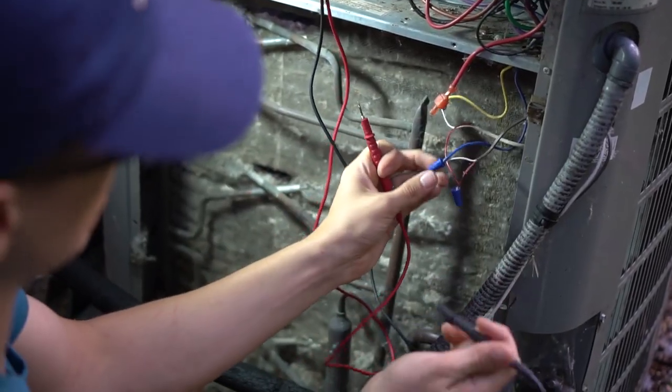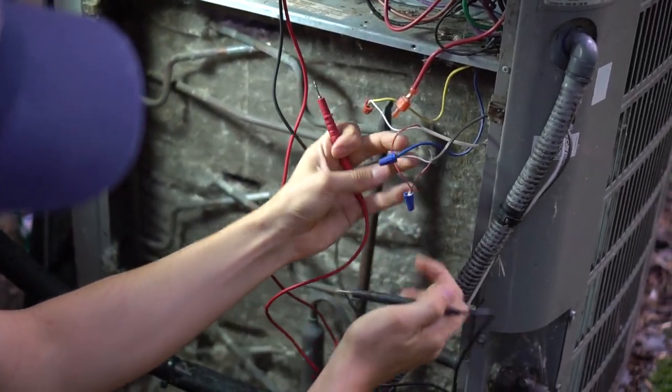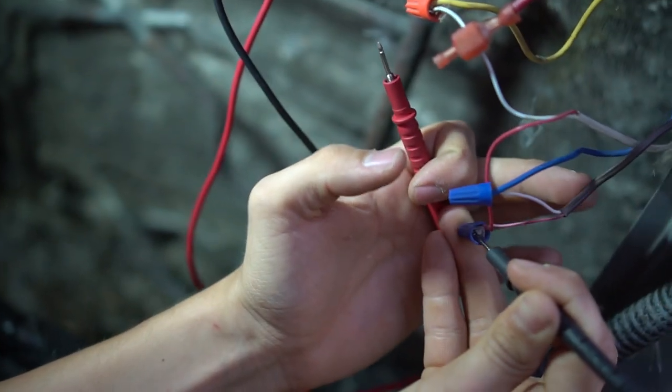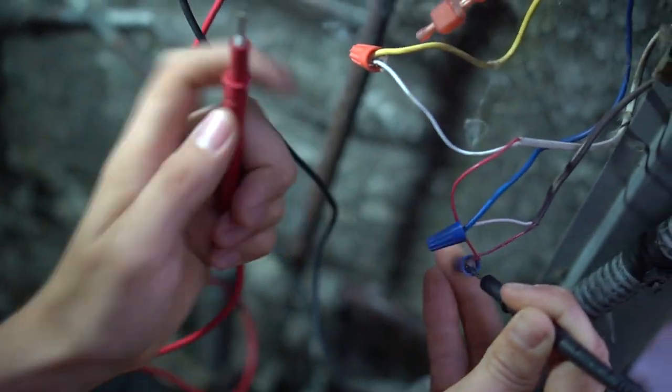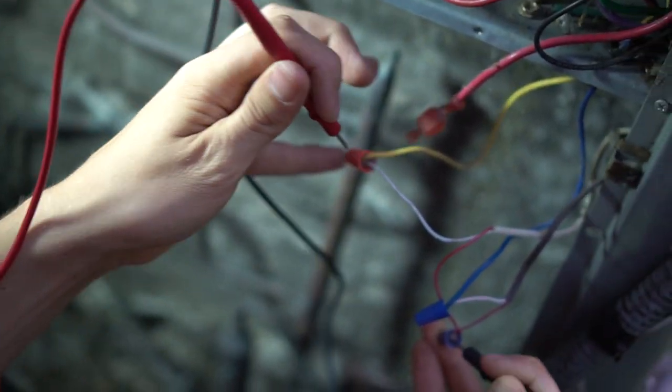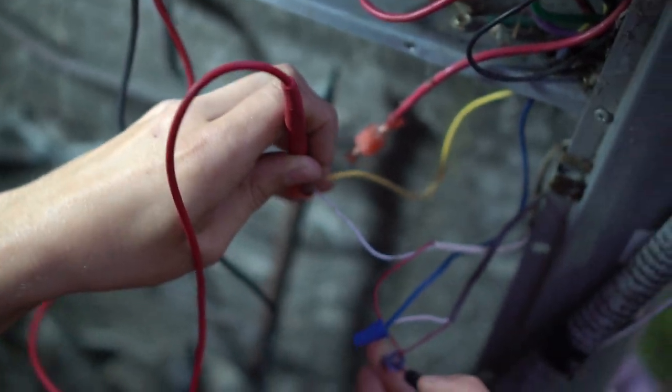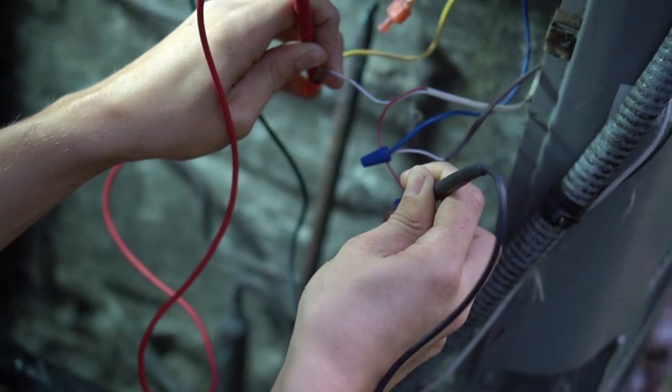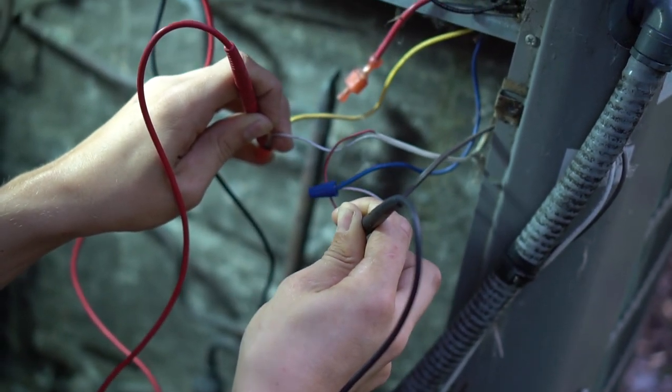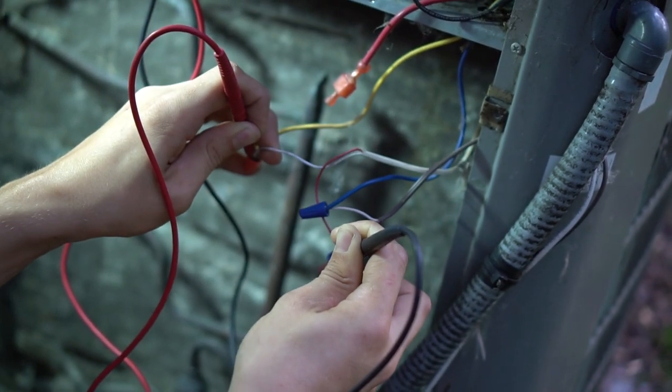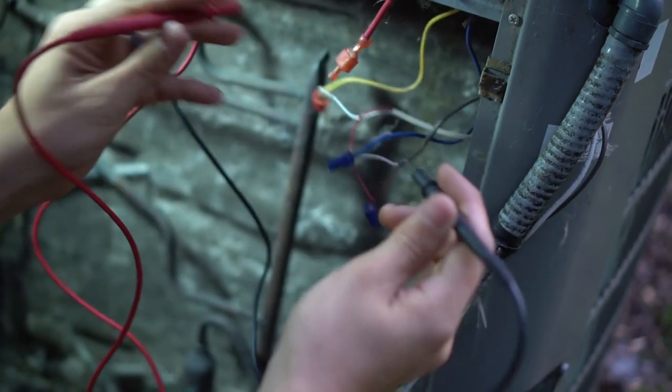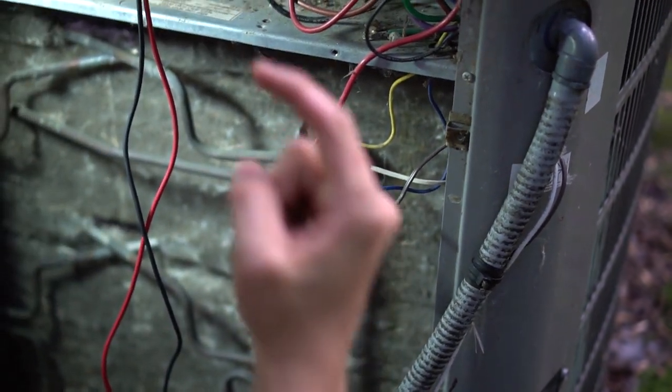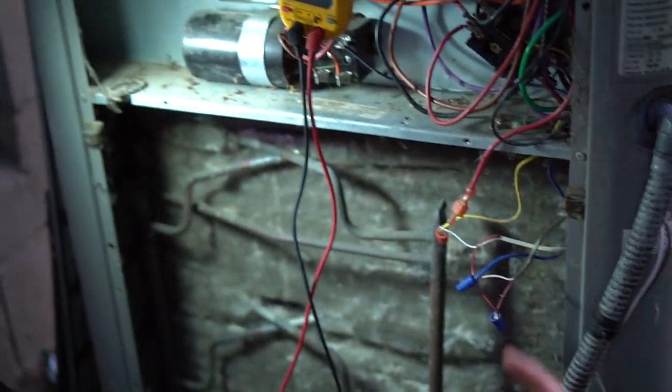So the power goes into the power saver switch through this red wire right here. So if you put one lead into the wire nut that's connected to the furnace control board thermostat wire, and then put your other lead on the other side of that power saver switch, you should have zero volts if the switch is closed. If you have 24 volts, that actually means that that switch is open and that power switch is defective or you're being cycled off during this time. So basically that power saver switch is simply wired in series between your contactor coil and the furnace control board.